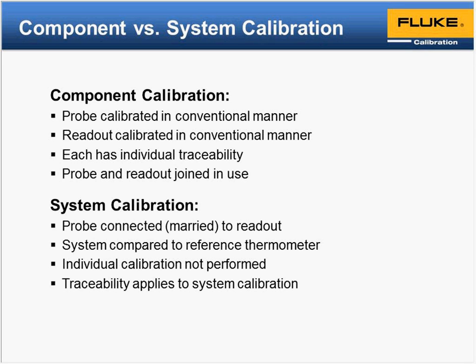So with those examples where you're calibrating each component, you can use each piece as needed and plug in other probes and readouts as needed. Once you've got two knowns, basically known goods on both pieces, the readout and the probe, they become a little more versatile in moving them around the lab and using them in different applications. With the system calibration, that's where we connect a probe to a readout, and this does happen even with some of the reference probes that come through our labs. Being a tech and knowing what you may be up against, it's not particularly my favorite method, but they work well. There's nothing bad, but you lose some of the versatility as far as being able to interchange another probe with that same readout.